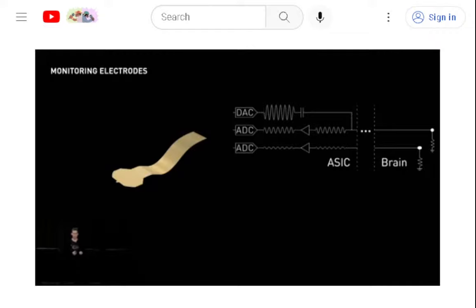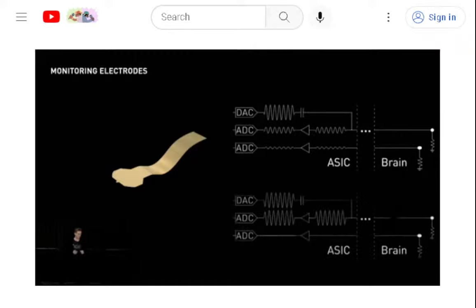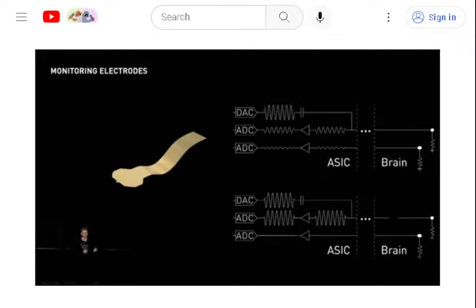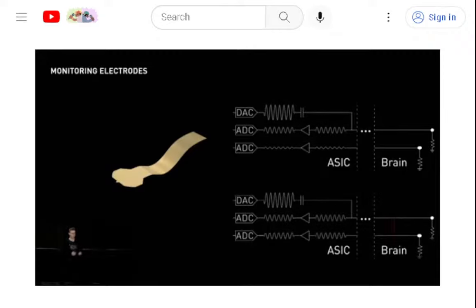And then we record, using our ADCs simultaneously, the response signal on both that channel and physically adjacent channels. Not only can we measure the impedance of every channel with this, but we can also map different physical phenomena to different characteristic signatures. So for instance, an open channel will appear as a very large response on the channel, and shorted channels will appear as a large response on neighboring channels.